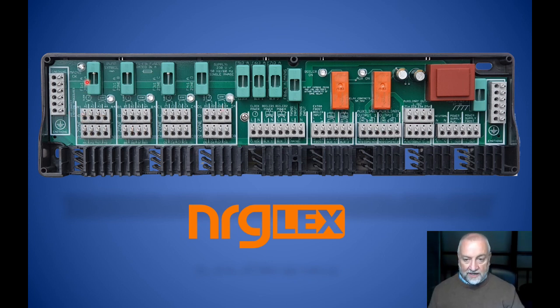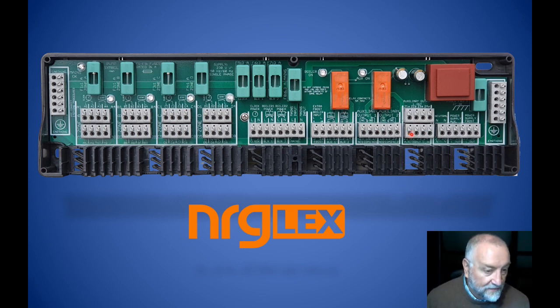The rest of them are just connections, a connection for power, a connection for your pipe stat or room stat, and a connection back to operate your pump or your time clock as well. So if you can understand the four connections here, so it would be A4, B4, C4 or D4. You also understand that this is the equivalent auxiliary input, auxiliary A1 or 1A, I think, and then 2A, 3A, 4A. What that means is that any one of those four inputs here causes that relay to close, and any one of those four inputs here, the A4, B4, C4 and D4, closes that relay. Now you can understand we've got a very, very simple process to control it. Of course, we've got earth blocks on the board as well, so it makes it extremely easy to logically sort out very, very neat wiring.